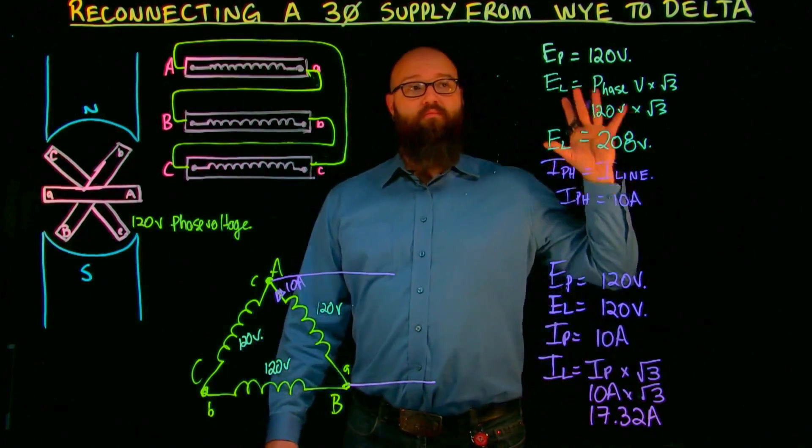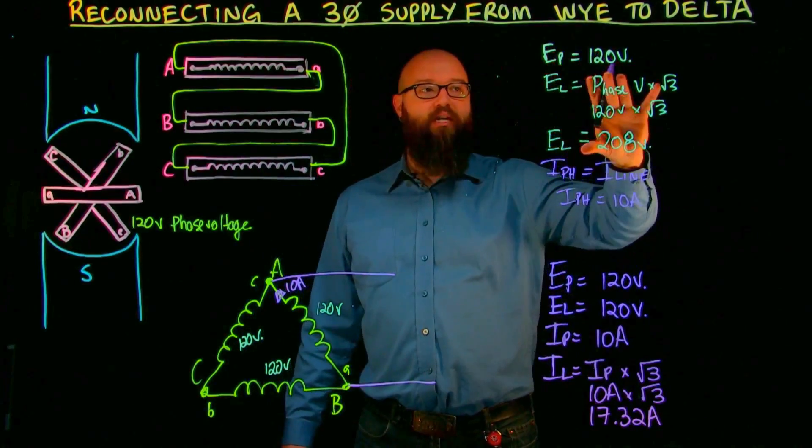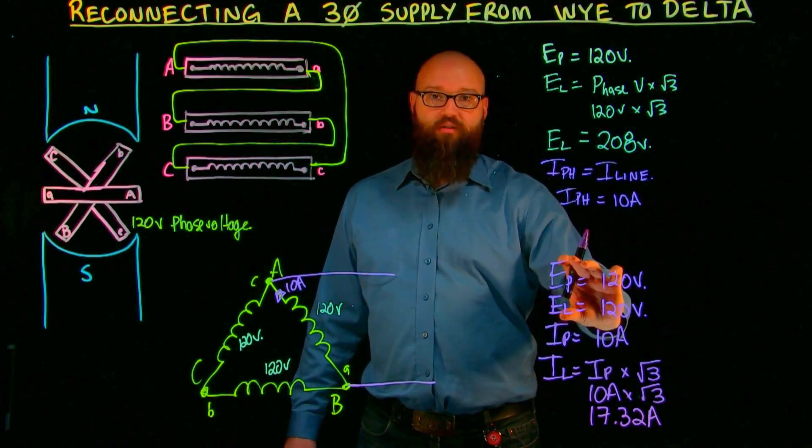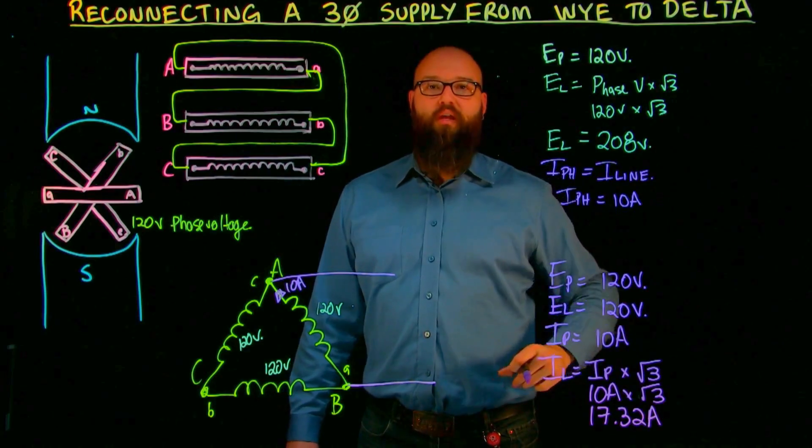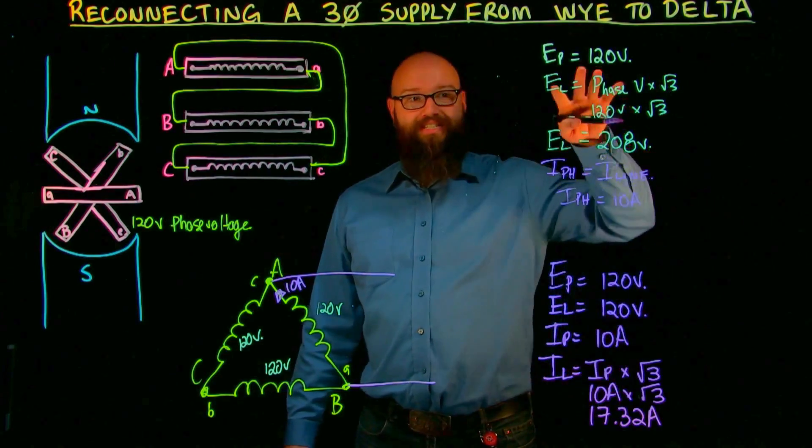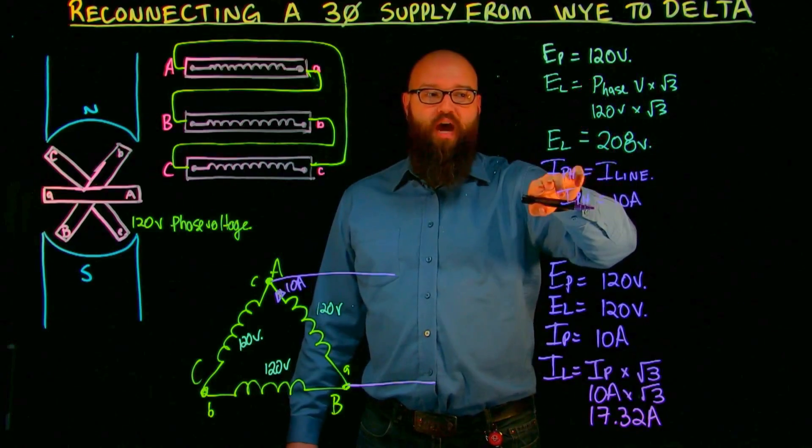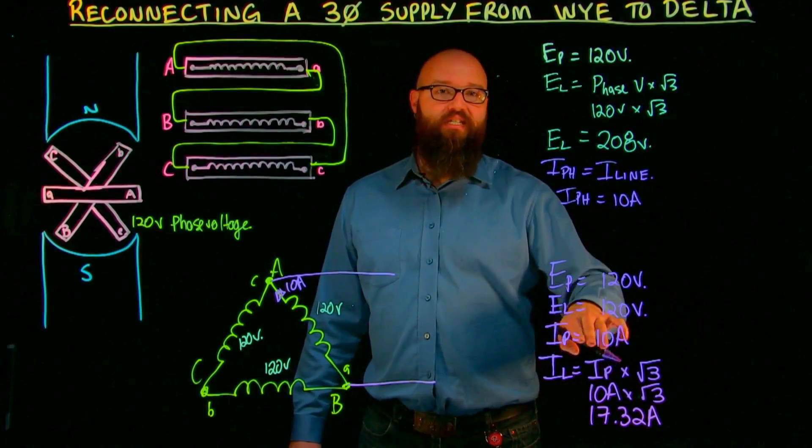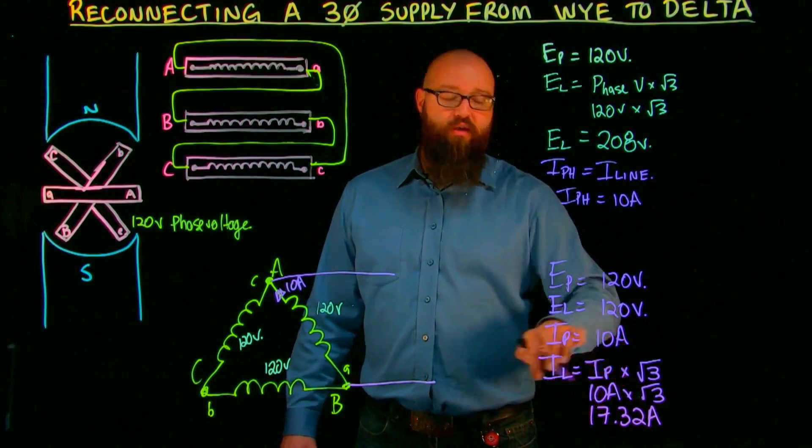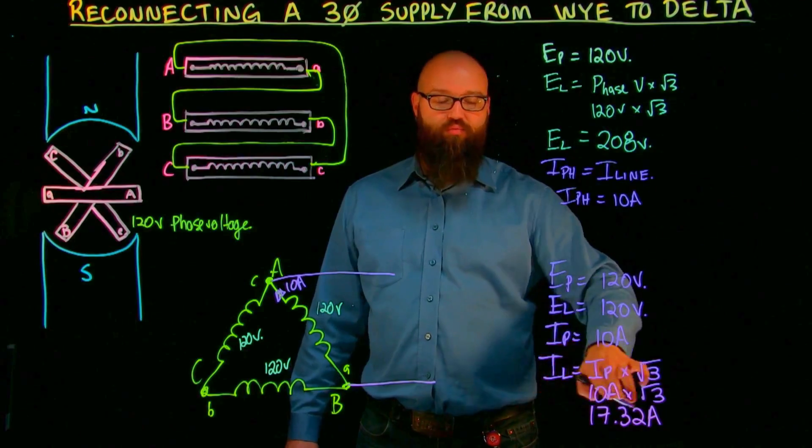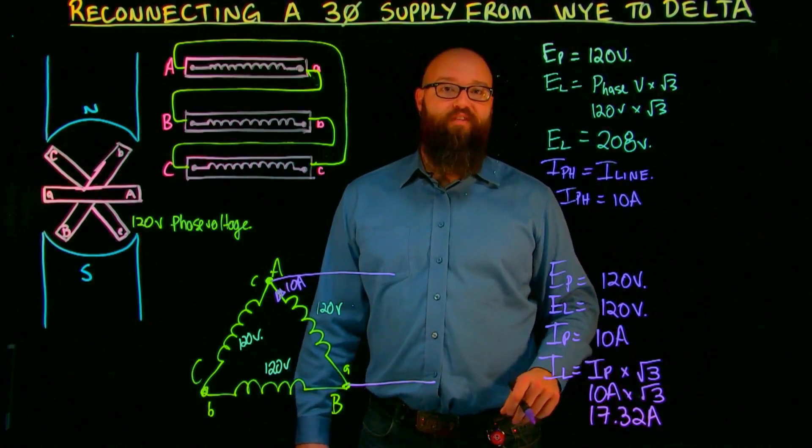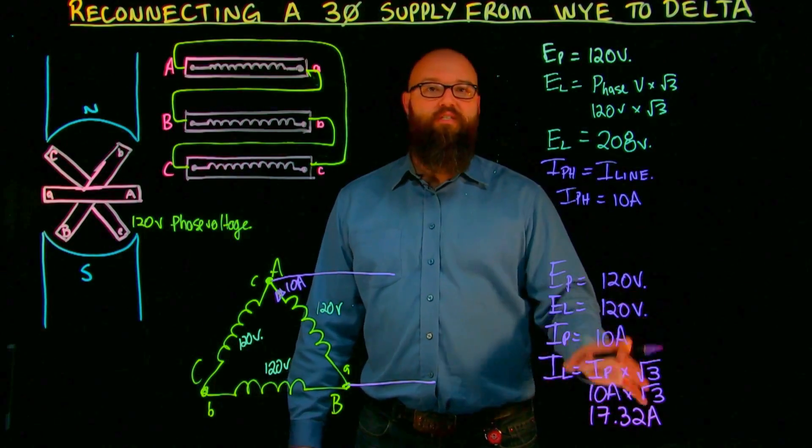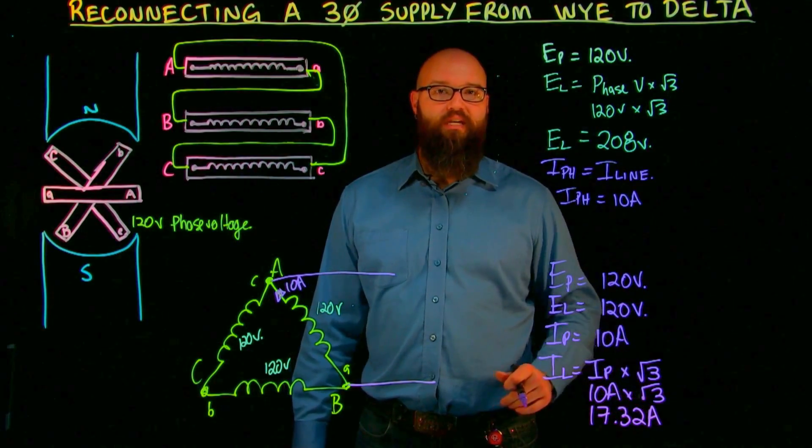So again, in a Y connected system, we have root three larger voltage line to line. In a delta connected system, my phase voltage is equal to my line voltage. In my Y connected system, I phase is equal to I line. In my delta connected system, I phase is root three smaller than I line, or you could say I line is root three greater than I phase. So we essentially, we increase the amount of current output on this system just by reconnecting it in a delta configuration.